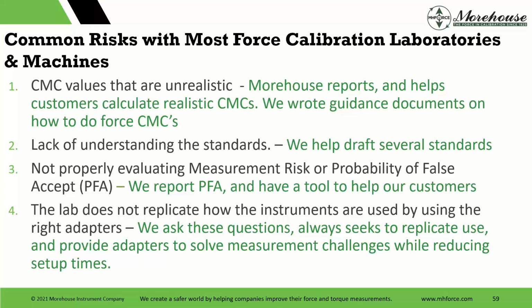We use method 5 of the ANSI Z540.3 handbook, and that's the most conservative method for guard banding. I'm in a big debate with this, because people assume things are centered, and I'm more on the single measurement side of things, the bench level measurements, where I'm not evaluating your whole process uncertainty. I'm just evaluating the equipment you have sent us at the time, and therefore we use a very conservative method. Because we don't know if you're switching pins, rotating pins.